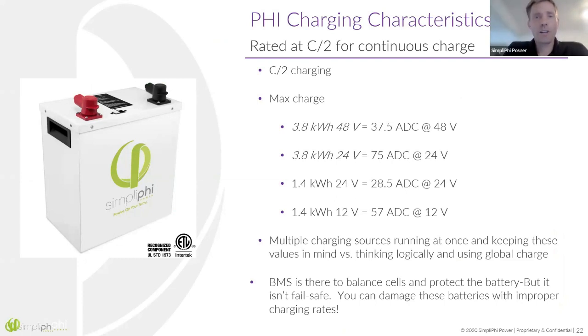But on the charging characteristics for a typical PHI battery, so I just showed you that battery has to be above 0 for charging to happen. We're going to charge it at a C/2 rate. And the maximum charge that that battery can take, this is the maximum safe charging rate, is 37.5 amps each. That means each battery. So if you have 2 batteries, it would double, 3 batteries, it would triple, etc. Typically, the charging equipment and not the battery is your limitation. But if you're using AC to charge, you want to be very careful.